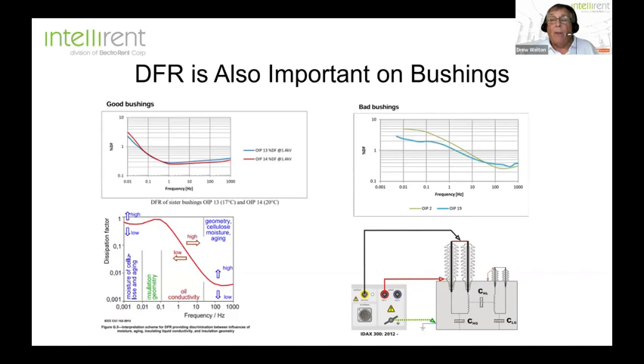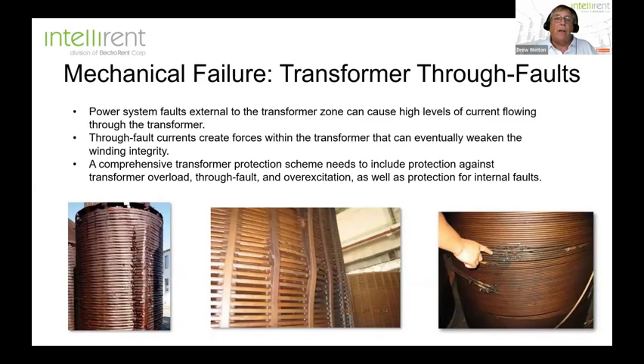Lo and behold, we can also do this test on bushings. So you get a much more accurate percentage of how much moisture is in your oil filled bushing. This is all done, number one for bushings, to help you determine when it's a good time to replace those bushings before you have catastrophic failure, or number two, to accurately determine if you need to mitigate the moisture in your transformer. The next thing I want to discuss, which is more in line with mechanical failures, is transformer through faults.